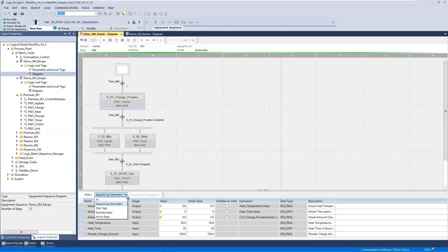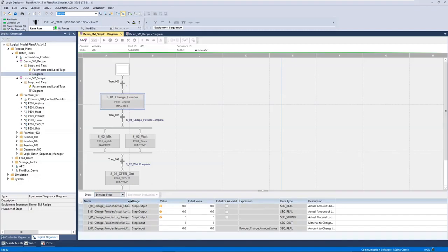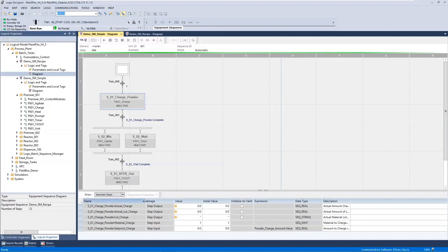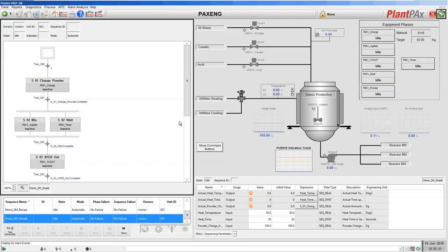For each step you can either use these recipe values or directly code a value. In this example we've selected the charge powder step and we can see the material to charge is set as a hard-coded value of one — which in our case is DI water — but for the set point we're going to use our recipe value, the charge amount.